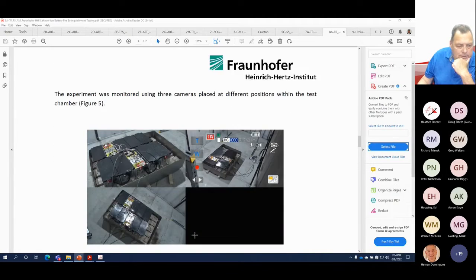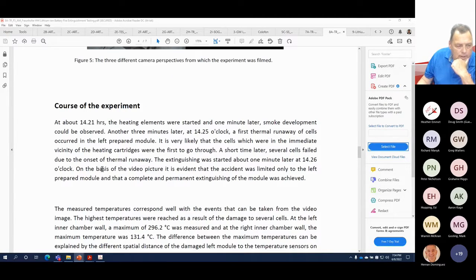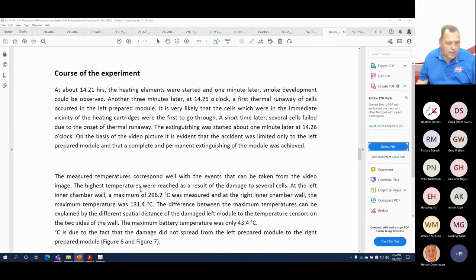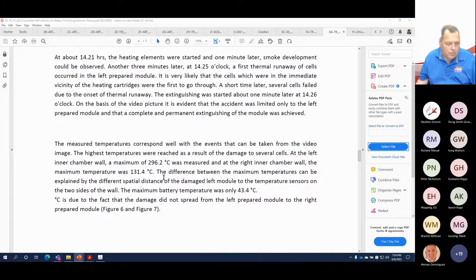This goes on to talk about how the fire was started at 21. We get the heating element, took about 4 minutes. We see the first thermal runaway. These occurred on the left side of the battery. Extinguishment was started 1 minute later at 1:26. Based on the video, it's evident that it was only limited to the left side. You saw the rapid extinguishment.